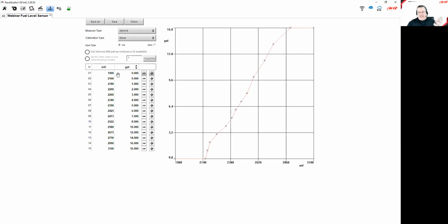I always tend to add one more data point that's also 0 gallons, but at 1900 millivolts. That way, if it ever drops below 2160—since it's electronic and sometimes reads 2150 or 2140—it won't start showing negative numbers if you didn't include this last line of data. So I'm telling it that it can drop all the way down to 1900 millivolts and still show 0.